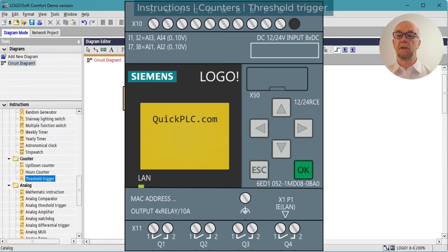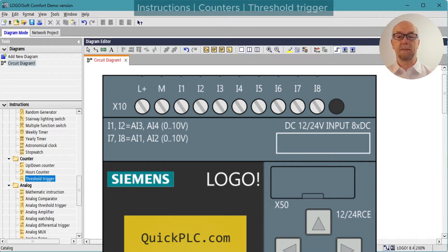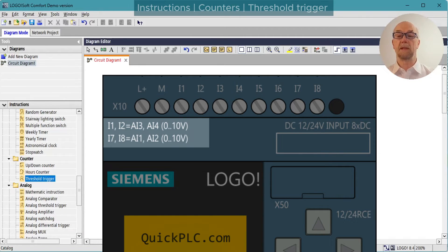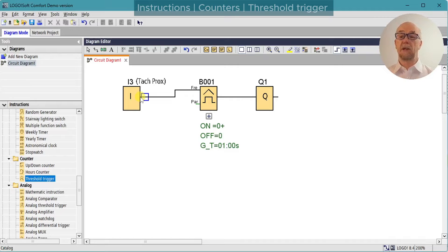Due to the design of the microcontrollers used internally, the purely digital inputs can be used as high-speed inputs, but those that are configurable as analog cannot. We can see from the LOGO markings that inputs 1, 2, 7, and 8 can be analog, so inputs 3, 4, 5, and 6 can be used for high speed. A further constraint is that the input must be connected directly to the high-speed input function block that uses it.